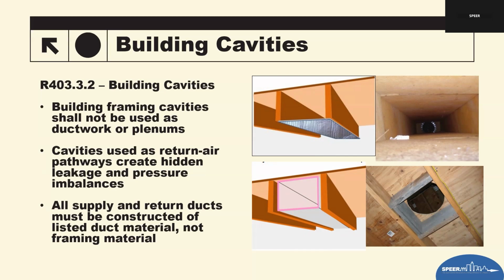But one of the most important ductwork requirements of the IECC is basically prohibiting the long-standing practice of using framing cavities as returns, pathways, or plenums. Of course, now it says they should not be used as ductwork or plenums. That includes supply and return ducts. They must be constructed of a duct material, not framing material.